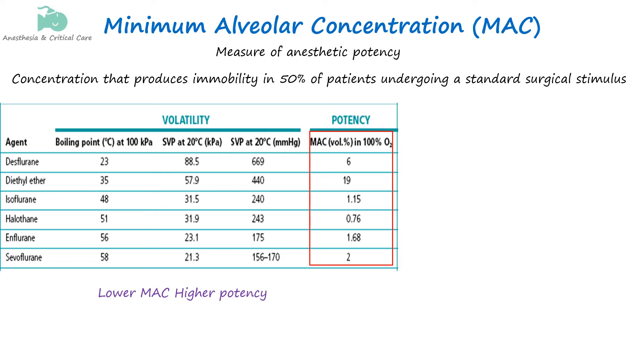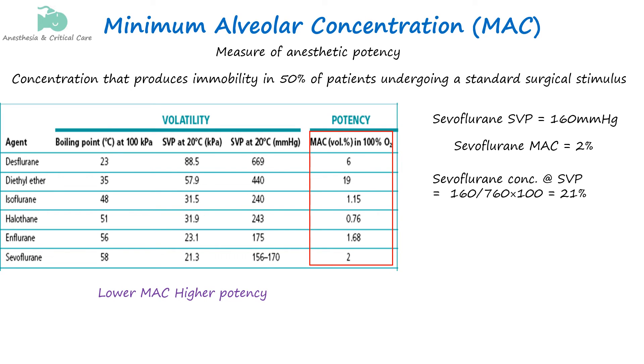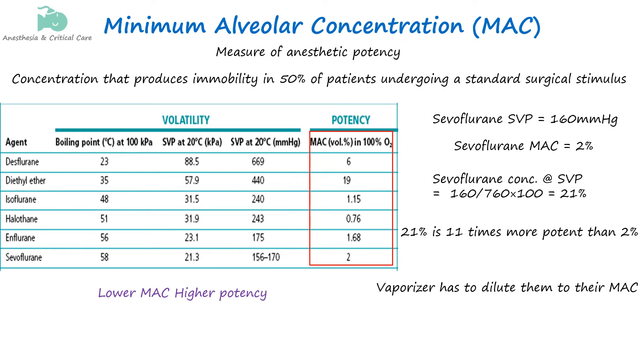Let's take sevoflurane as an example. It has an SVP of approximately 160 mmHg at 20 degrees Celsius, and a MAC of about 2%, meaning it is potent enough to induce anesthesia at this low alveolar concentration. When sevoflurane is fully saturated at atmospheric pressure of 760 mmHg, the concentration would be around 21% — approximately 11 times more than the 2% MAC value. Therefore, vapors must be diluted by mixing with oxygen and other gases to provide clinically meaningful concentrations.